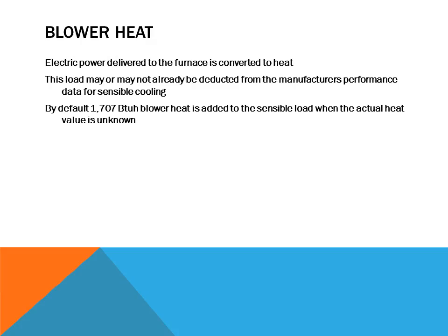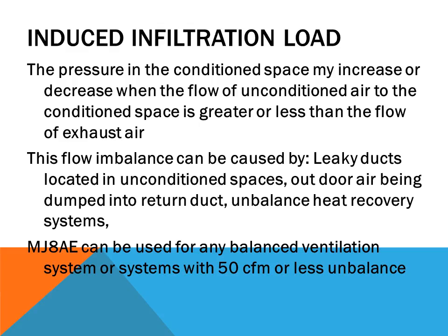So as we look at this, we know that we have heat load from other types of loads, sensible heat loads, from other things that we may not consider, but it's still there, such as even a blower. A blower, because of velocity and the heat from the motor operating, can generate a certain amount of heat energy that we need to consider also. It's not that large of a load, but it can make a difference with other smaller loads. It can affect how the cooling in the summertime will need to be sized for the system. So considering these loads, even from blowers, is extremely important.